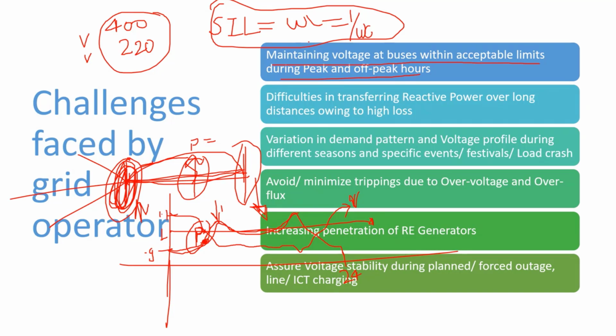So the first challenge is that you have to maintain the voltages within an acceptable limit during peak and off-peak power hours. During different durations of the loads, you have to maintain the voltage near 1 per unit. There are difficulties in transferring reactive power over long distances owing to high losses, right? So we can't transfer the reactive power over long distances. You have to do all this compensation at the local level.